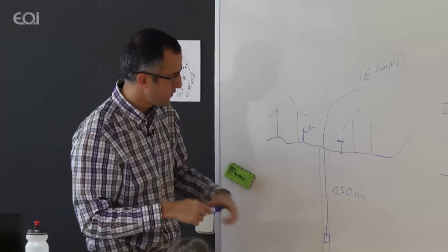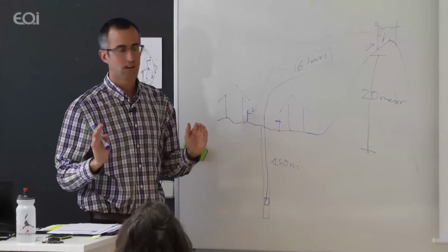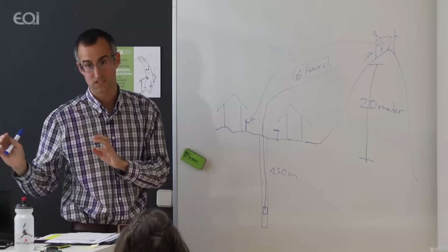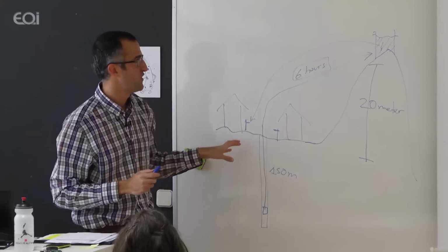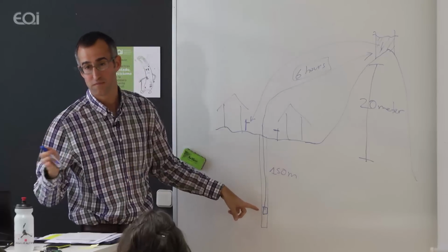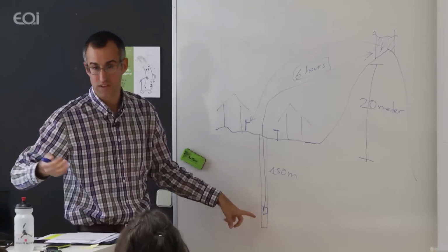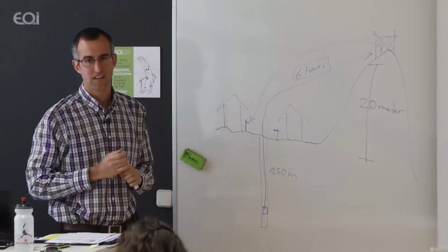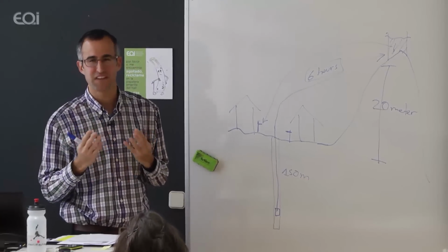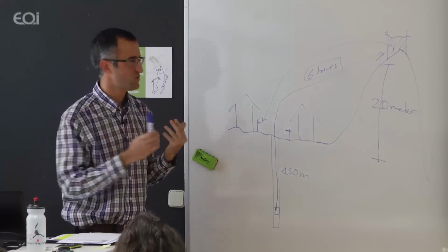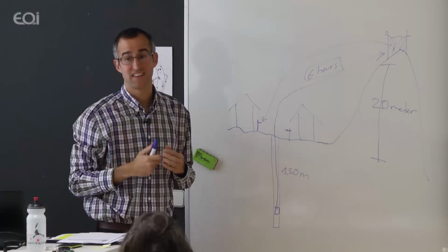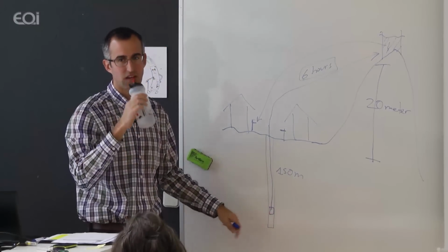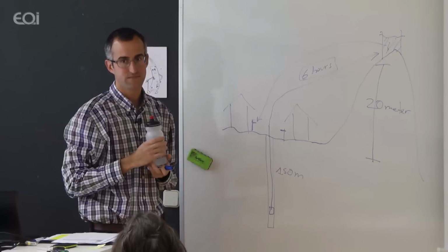So instead of working the whole time at 150, we were working only once a day. And when the electricity was cheaper during the night, we were not breaking the pump in 1 year, but it was going to work for 20 years. And then during the day, we had it pressurized. Do you understand? Yeah. But it's a very good question, because maybe it's not so obvious to work a little bit more, but it works, because the very expensive thing here is the pump, and if you have to be changing the pump every year, okay.